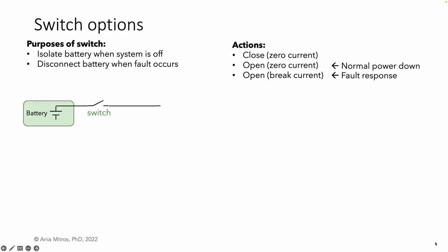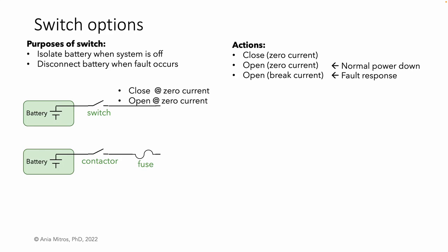The simplest architecture is a simple switch. Many switches aren't designed to open while current is flowing, or can only open with a small current. For small batteries and small systems where overcurrent protection isn't critical, this may suffice. For systems requiring overcurrent protection, we can upgrade our switch to a contactor, which is a relay designed to open while current is flowing. All contactors are limited to some maximum current at which they can open.